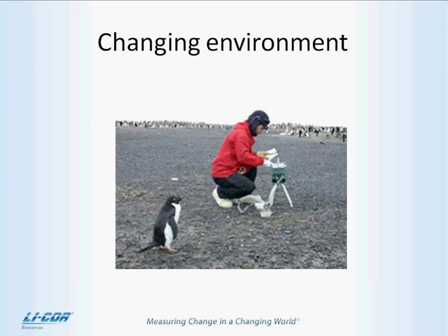Thanks, Elizabeth. Before Tanvir takes his place, I do have a question from the audience, and that is, can I put just the sensor head in a growth cabinet to change the temperature? Oh, that's a good one. And the answer is no, it's not really a good idea to put just the sensor head in the growth cabinet. What you want is to have the entire instrument at one temperature.